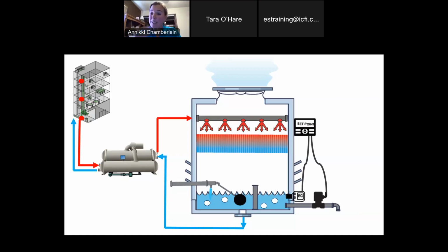So basically this process goes on and on, over and over, removing heat from the building, giving it to the cooling tower, monitoring the mineral concentration in the water, draining the tower, and refilling it. Now we'll talk about cycles of concentration in a second, but the number of times we reuse that water before we drain and fill the tower is called our cycles of concentration. And that's kind of our main efficiency metric that we use to understand how efficiently our tower is operating.